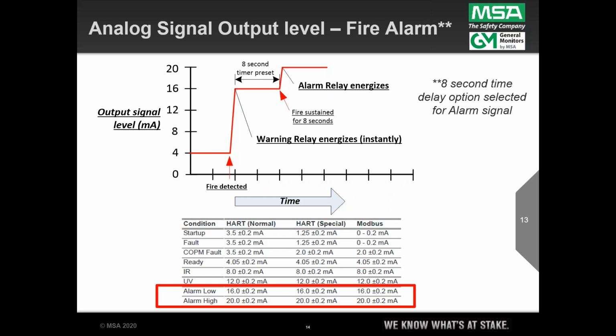It's time, right? So if we follow our little red graphic line from left to right, 4 milliamps, everything is good until the fire is detected. You see the little red arrow, and then boom, we have a step change up to 16 milliamps. At that point, when the analog value reaches 16 milliamps, the device energizes that instantaneous alarm relay, right? So those two things happen at the same time: 16 milliamps and the instant relay energizes.